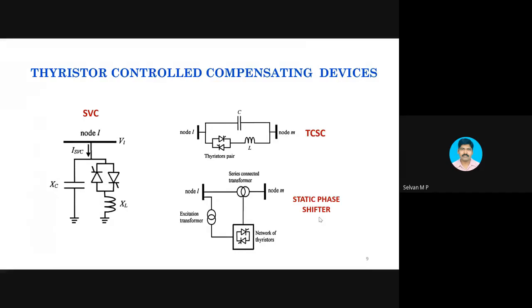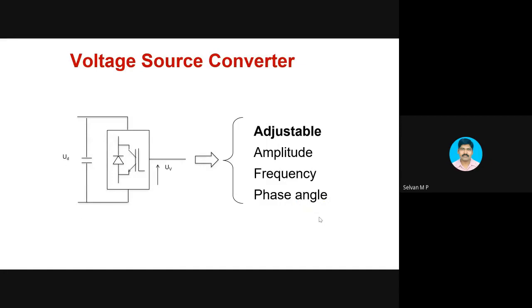Of course, you can get a variable output from the capacitor, but still it depends on the operating voltage. Reactive power output from a capacitor is always V squared by XC. So it depends on voltage. If the voltage goes low, though it is a static var compensator or a simple capacitor, the reactive power output is going to reduce because it depends on the voltage. So we need a reactive power compensator which does not depend on the voltage of the connected bus. Such a system should be developed. That is possible with the help of a voltage source converter.